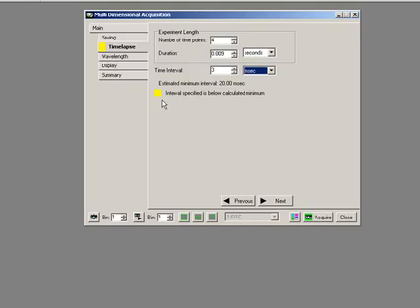Now, you have to bear in mind that's good, but it does not take into account any filter wheel movements, any stage movements, any Z movements. So it is only a useful tool if you were doing time-lapse alone. If you need to calculate how long an acquisition run takes, you should really do that acquisition run and work it out.